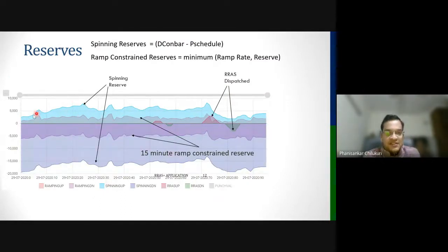When I say reserves, there are two kinds. One is the normal reserve, the difference between P max and the P schedule - that is the reserve. What is the maximum a generator can generate, and what is the present operating point of that generator? The difference is the headroom available for the generator to generate, that is up reserve. Similarly, there is a down reserve, the present operating point minus the minimum till which the power plant can generate, that is down reserve.